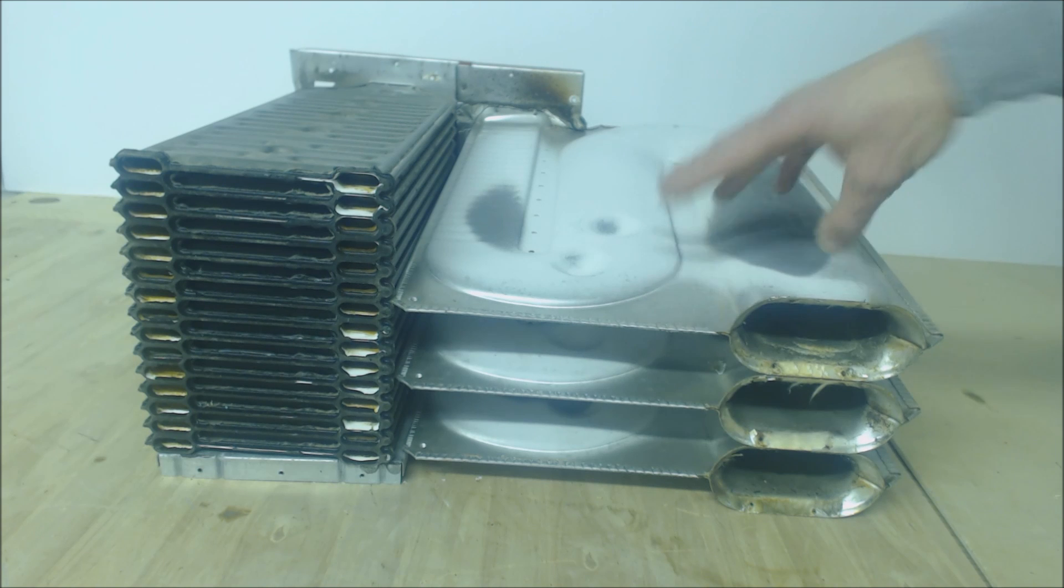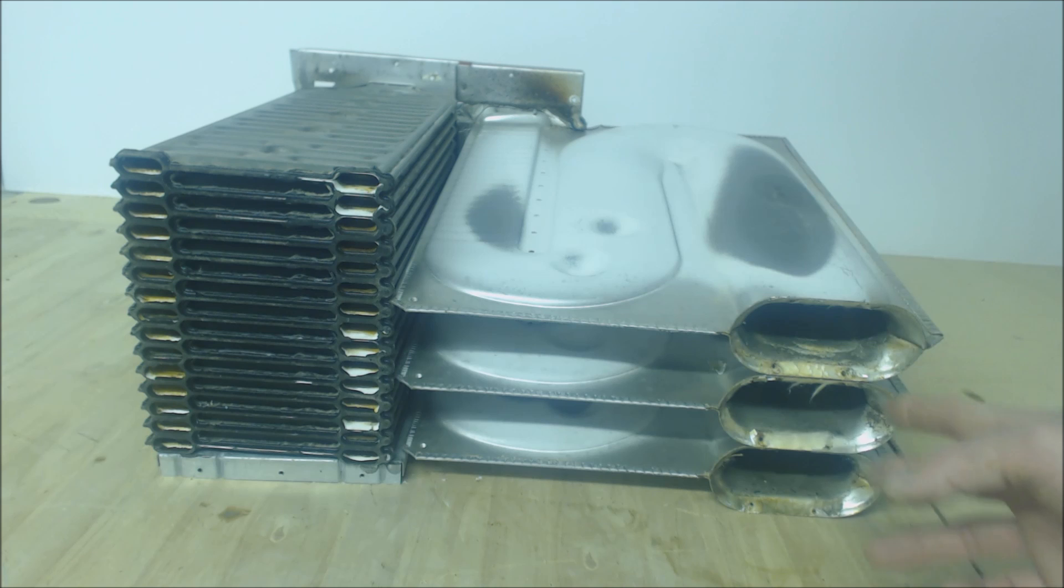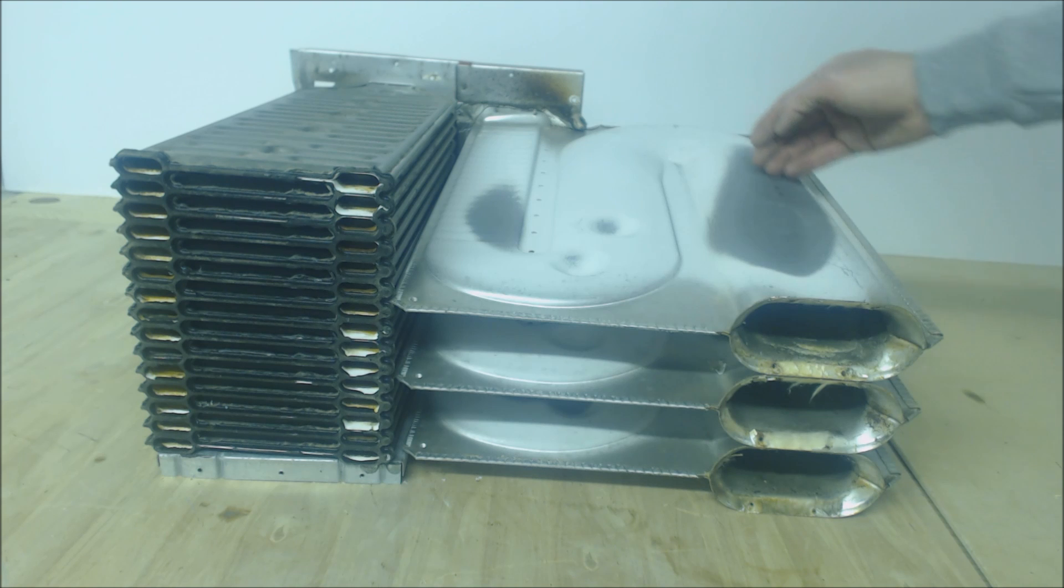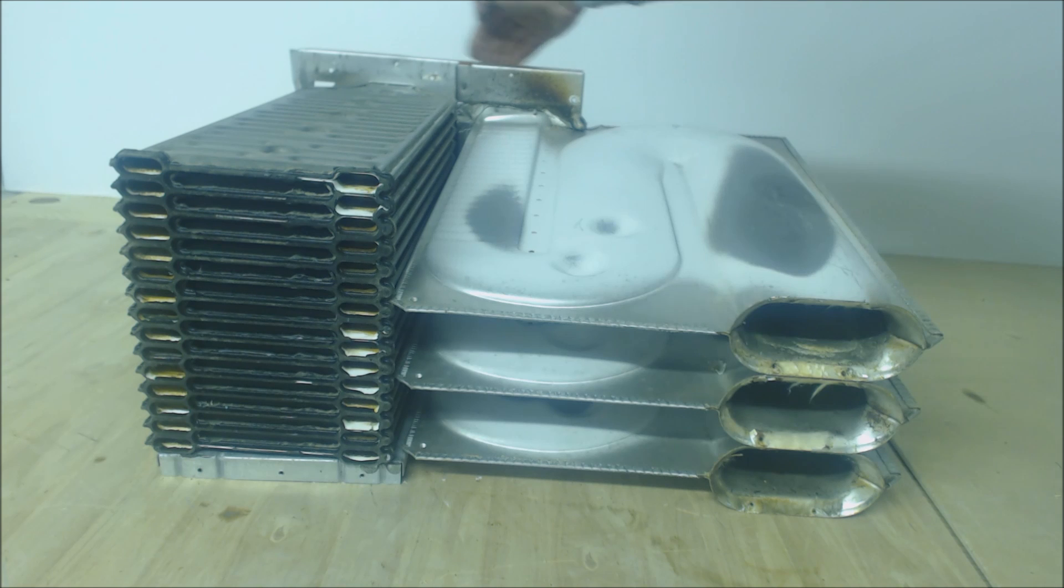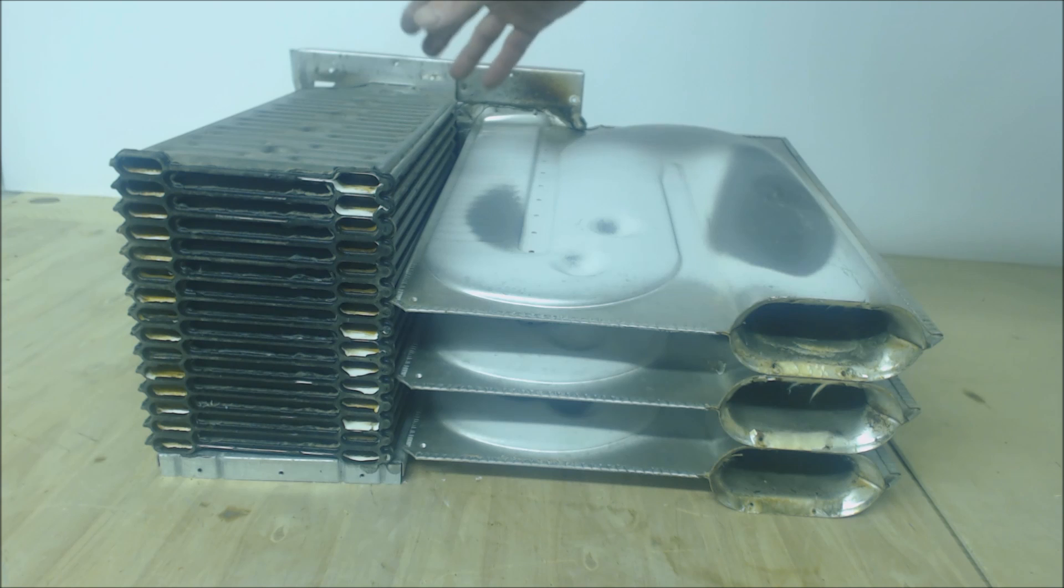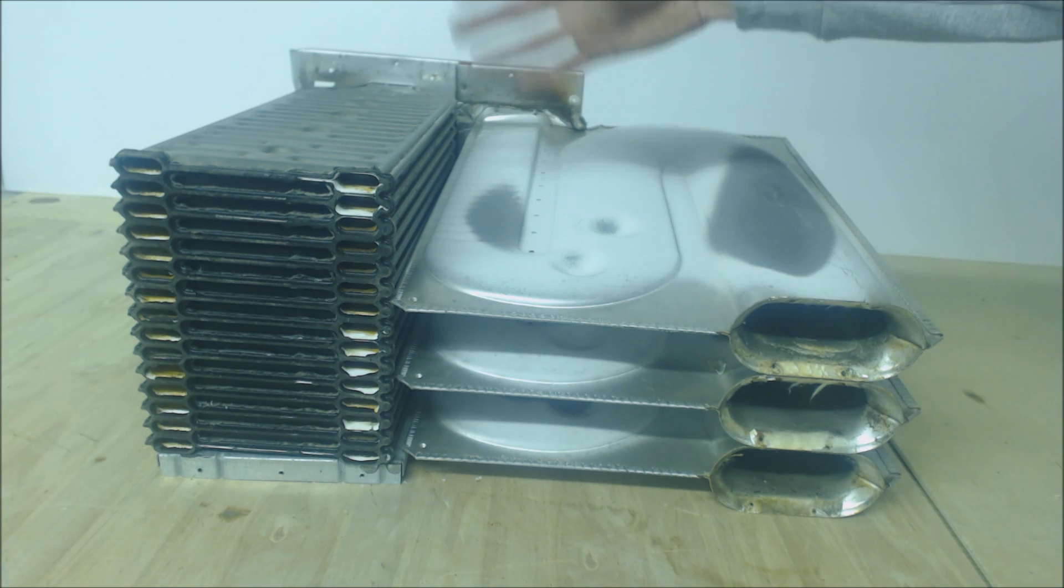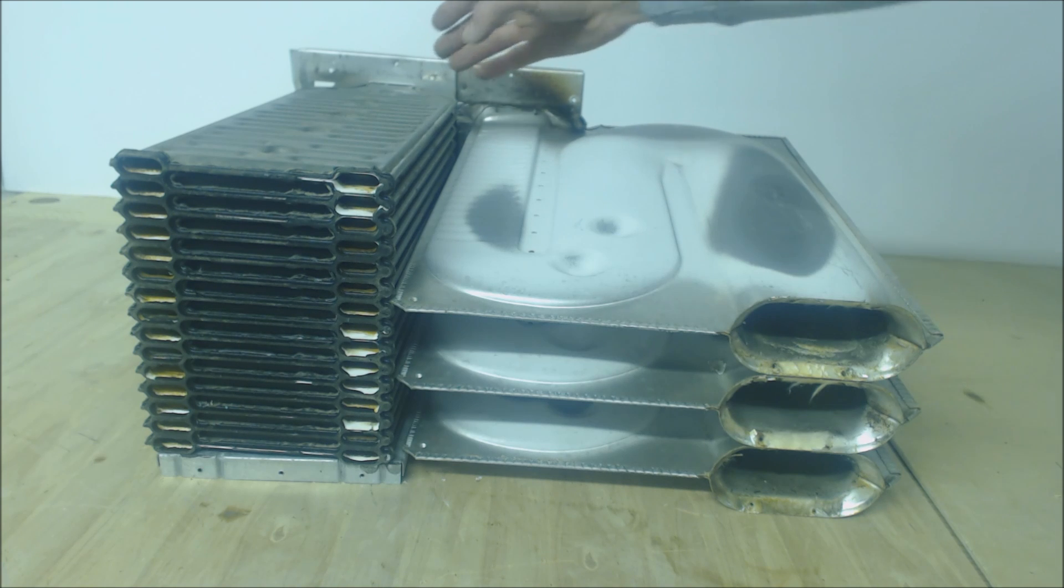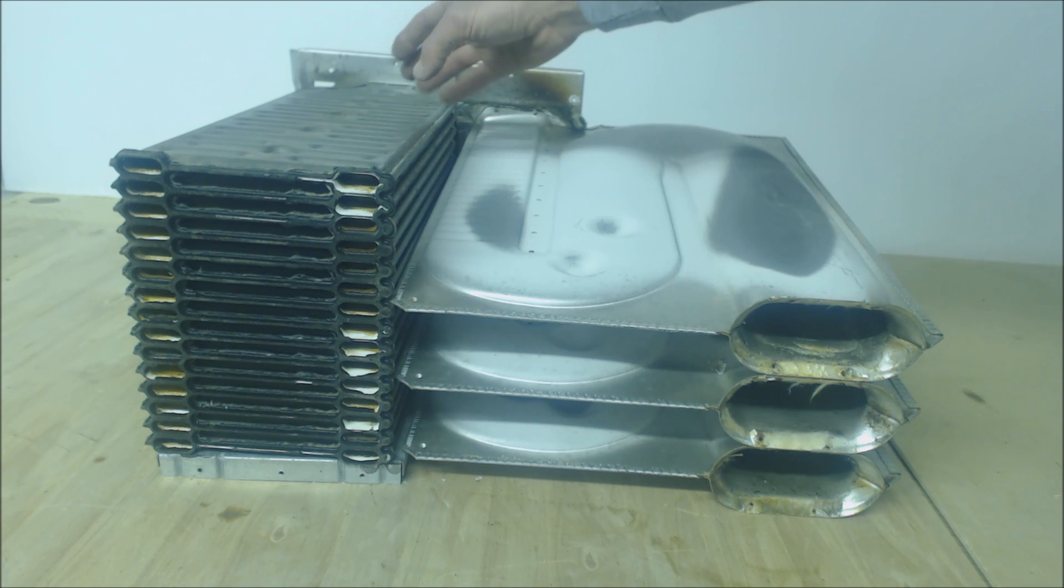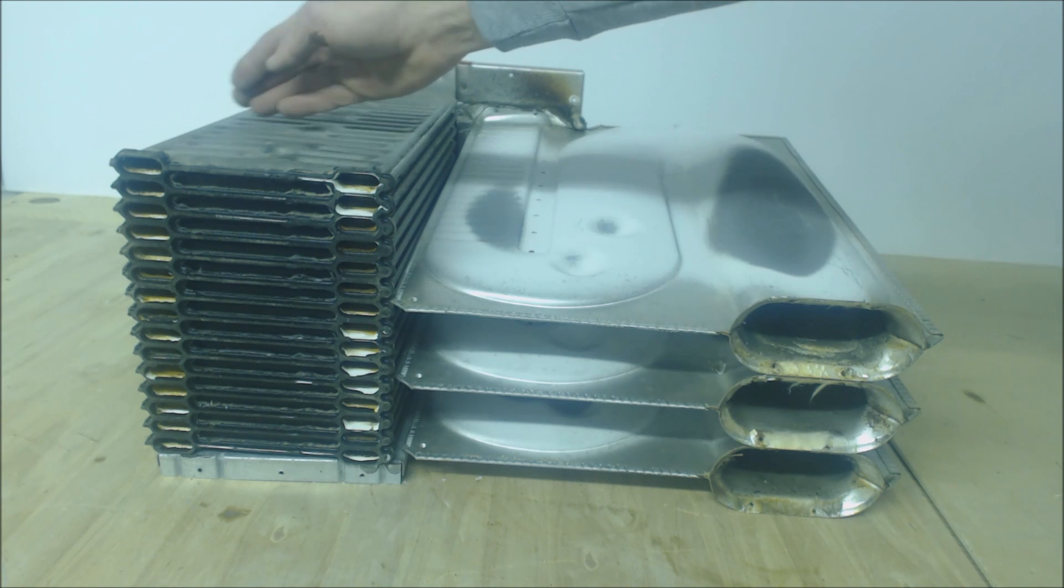This one right here is the secondary heat exchanger. This is the primary heat exchanger, where the combustion gas mixed with the air and ignition source. You'd have your flame and exhaust come over to here. The exhaust gets sucked through this heat exchanger, then to the back, and over to meet the secondary heat exchanger. Here is where you're absorbing heat from water created during the flame process. Water vapor is carried in the exhaust, and you're cooling the exhaust and water down so much that you condense the water in here, then it trickles out of the system.